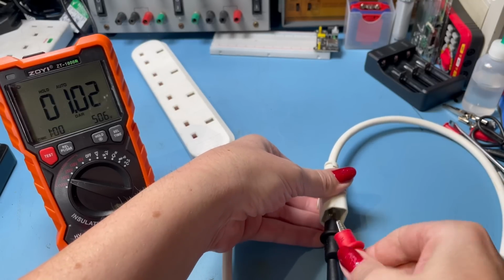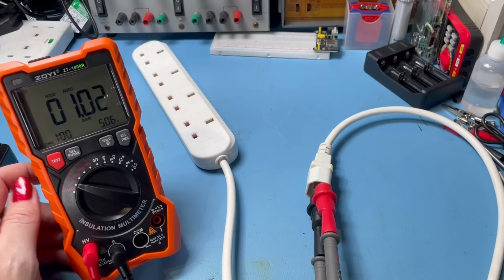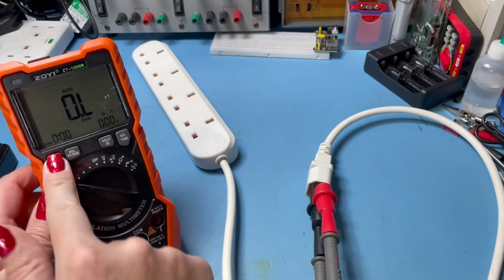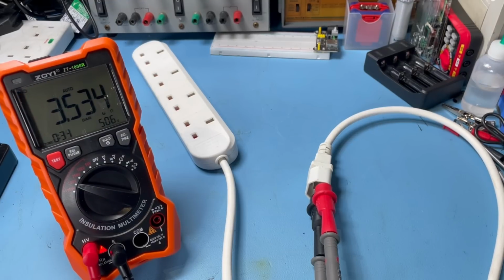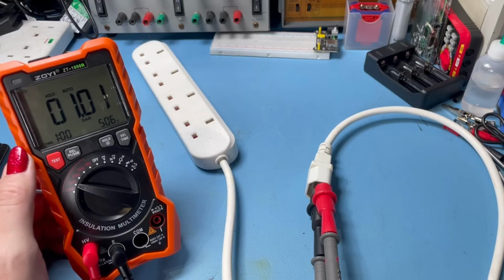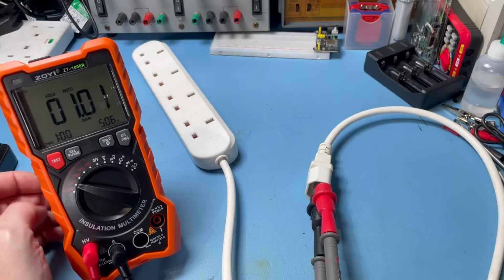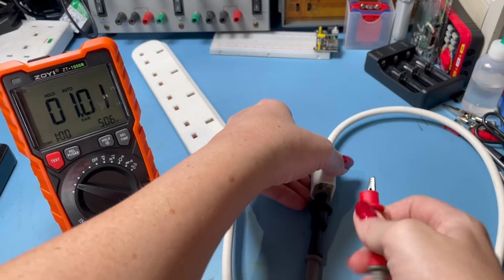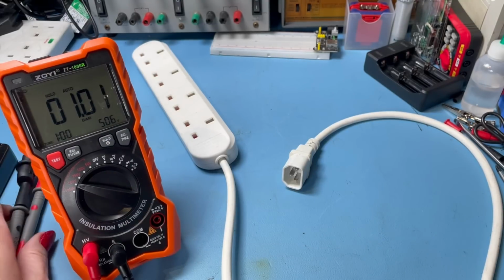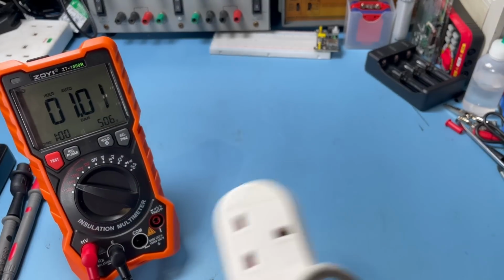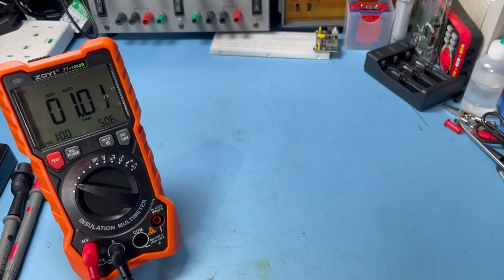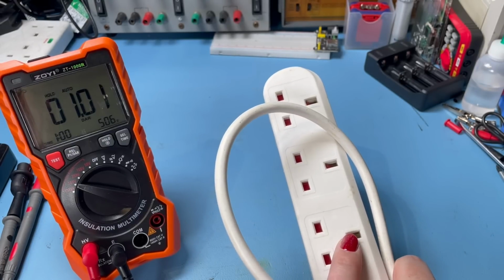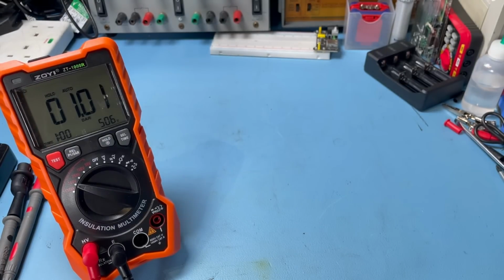We're now going to go between live and neutral. Okay, same test again, live to neutral, 500 volts, DAR, go. Yeah, you can see we had a higher resistance there between live and neutral, nearly 3.6 gigohms. And we finished with a DAR of 1.01. So they're all fairly similar readings on this cable. I would go ahead and say that cable is absolutely fine to use. And I have been using it. I can confirm that as well because I checked this on my Robin PAT tester and it did get a pass. So we're looking good.